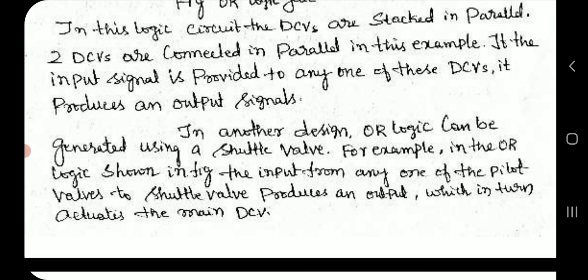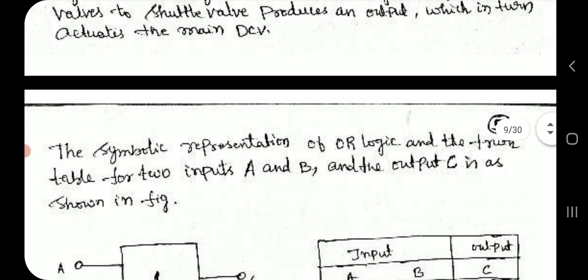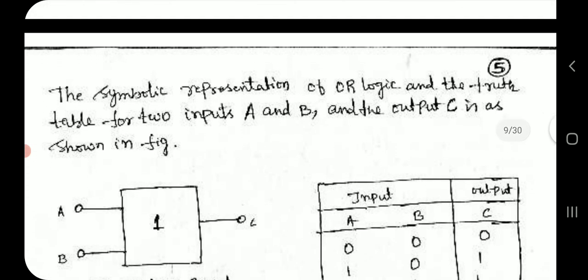In another design, OR logic can be generated using a shuttle valve. For example, in the OR logic shown in figure, the input from any one of the pilot valves to shuttle valve produces an output which in turn actuates the main direction control valve. In this example, the symbolic representation of OR logic and the truth table for two inputs A and B and the output C is as shown in figure.